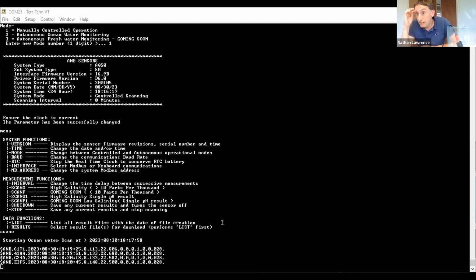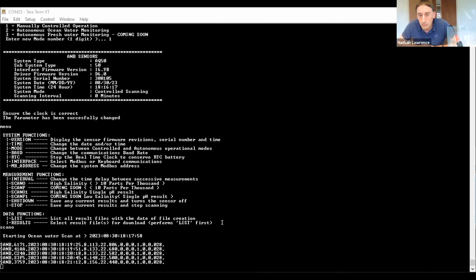Typically it takes around 90 seconds for the first pH sensor to respond. That's really because when we turn on the sensor and do the first scan command, we're looking at the reference element and understanding a reference electrode potential. We do the checks and validations on that reference potential first before we take the pH measurements, and then we can correct those measurements for any changes that we've seen in the reference element.